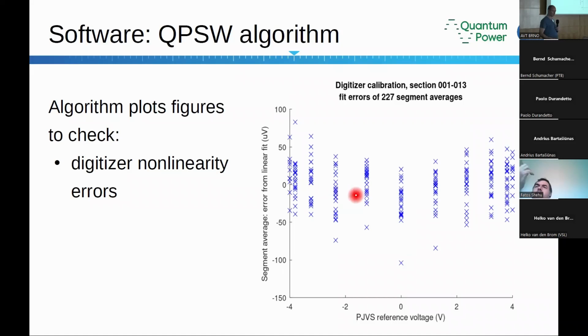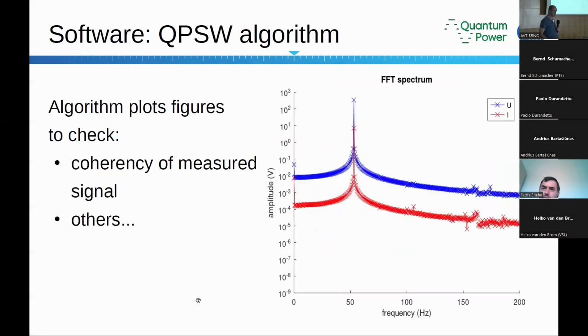It can also plot the nonlinearity of the digitizers, so you can check if there is some big issue or not. In the case here there was some error, because 50 microvolts is too much. You can also see the spectrum to see if your measurement is really coherent or not. In this case, you can see a non-coherent measurement. So you know that you cannot use a simple FFT; you need at least a windowed FFT, or time domain integration, or some other better method.